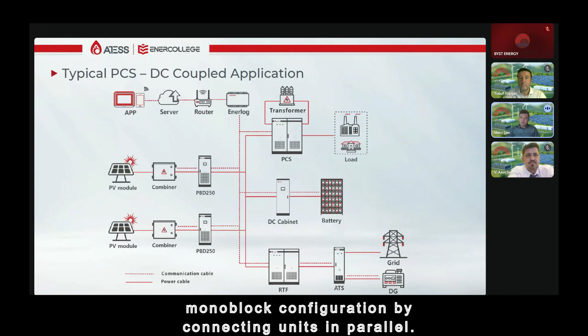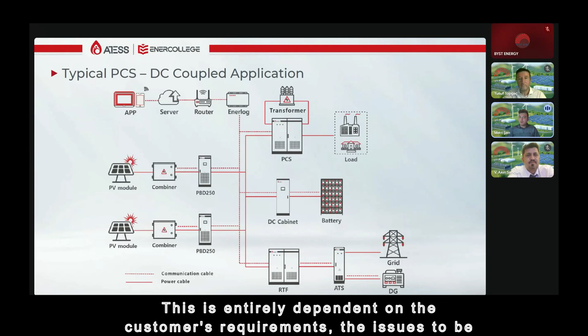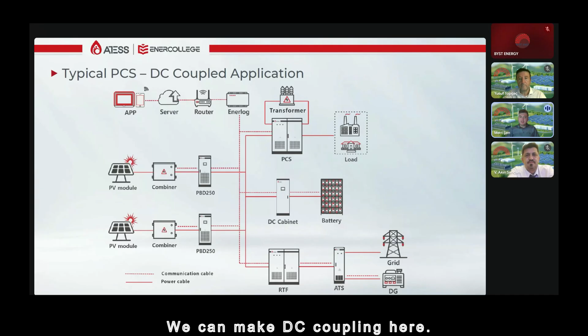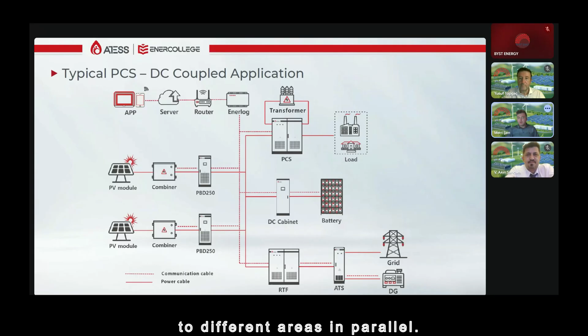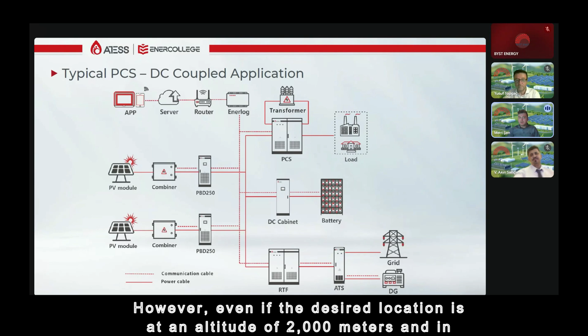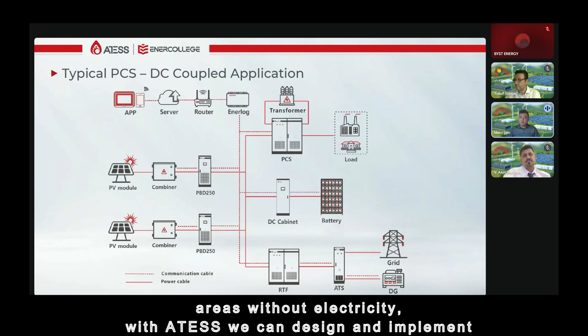We can increase this power from 100 kilowatts to 1 megawatt in a monoblock configuration by connecting units in parallel, scalable up to 8 megawatts. This is entirely dependent on the customer's requirements, the issues to be resolved, and the scale of the project. We can make DC coupling here. We can also provide power from a single common pool using AC coupling to different areas in parallel. As we mentioned, this is entirely based on the request form we receive after communicating with our customers. It depends on the information we gather from them regarding our design. However, even if the desired location is at an altitude of 2,000 meters and in areas without electricity, with ATESS we can design and implement high-power ESS containers to provide a solution.